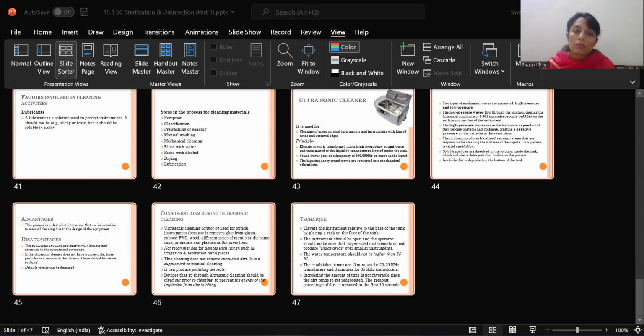As for restricted flow, the sterilant must come into contact with the microorganisms. Device designs that prevent or inhibit this contact, like sharp bends and blinded lumens, will decrease sterilization efficacy. Device designs and construction thereby affect the compatibility with different sterilization processes and affect the efficacy of the process.